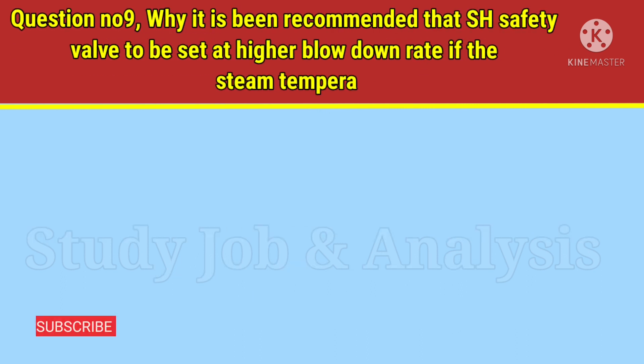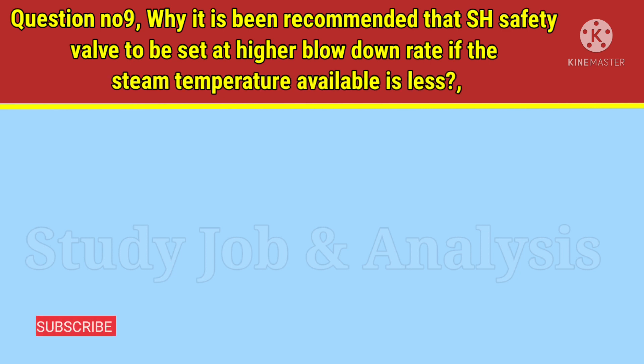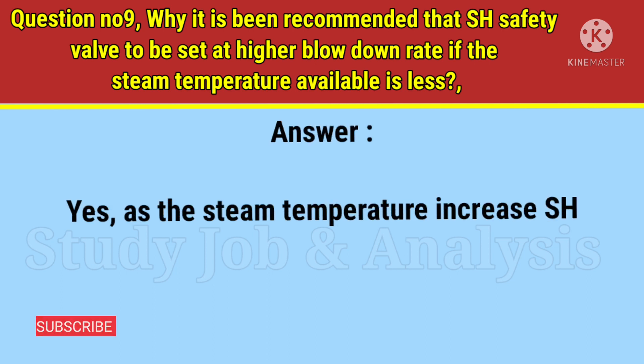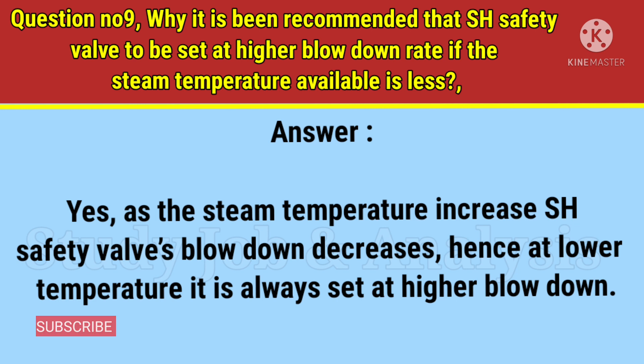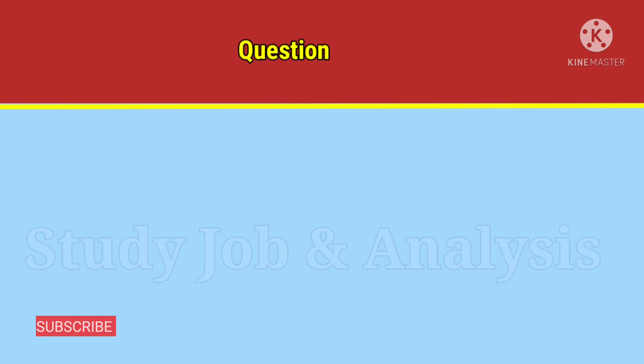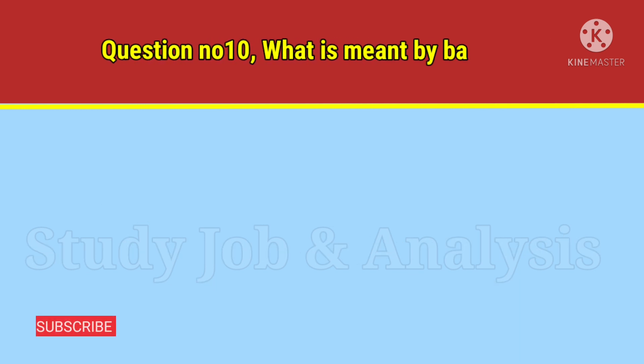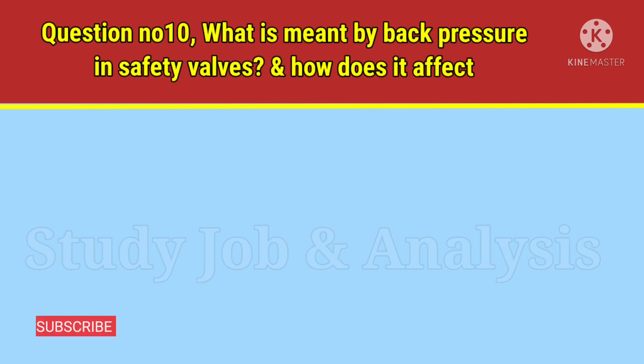Question number nine: why is it recommended that the superheater safety valve be set at a higher blowdown rate if the steam temperature available is less? Answer: As the steam temperature increases, the superheater safety valve blowdown decreases. Hence, at lower temperatures it is always set at a higher blowdown rate.